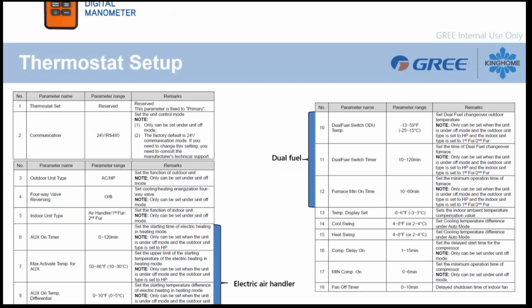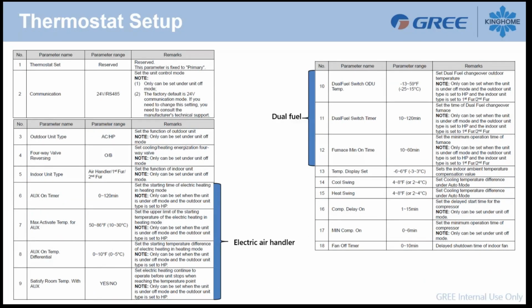I just want to also talk about the KingHome thermostat. The KingHome thermostat here has 2 different configurations that you can do. You can select inside the thermostat if you have a gas furnace, or you can select an electric air handler. Inside the configuration, some settings are related to the electric air handler and some to a gas furnace. So for an air handler, we will focus on adjusting parameters 6 to 9 here, only for the electric air handler. So there are different applications here that we can select.